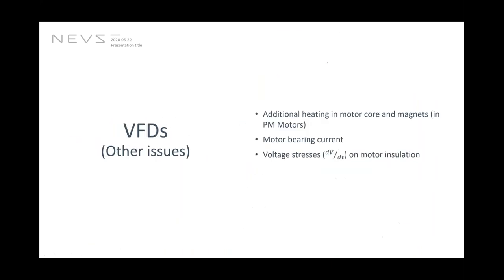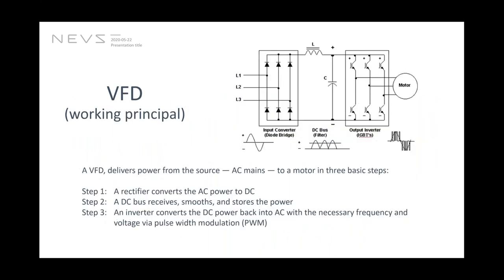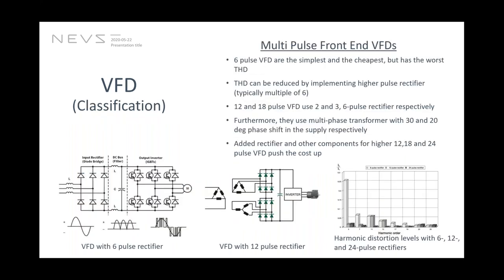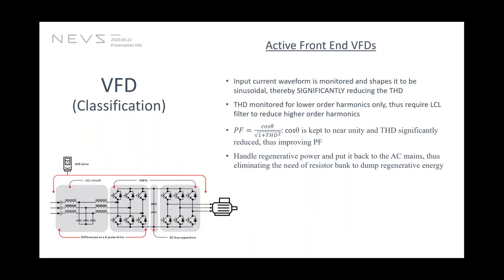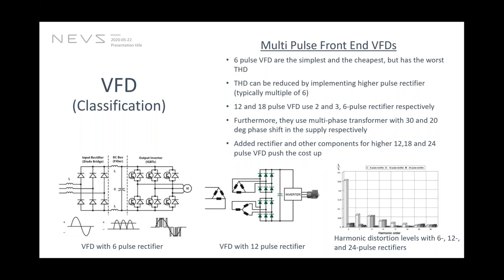Basically, if you look into the six pulse and the multi-pulse system, you do not have active switches like in the active front end to push the power into the main supply. Then somewhere at the DC bus filter, you need to implement a resistor. I have to look into it actually, because the dumping resistor, where is it kept? I have no idea about it actually. But the basic thing is that because of the diode, you cannot have the energy flow into the lines, so you must somehow implement a dumping resistor if your motor is regenerating some power.